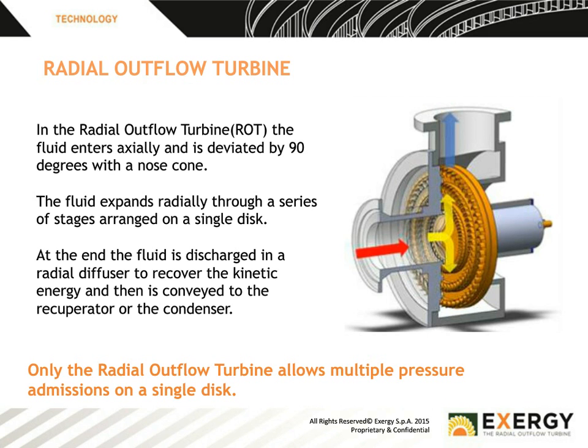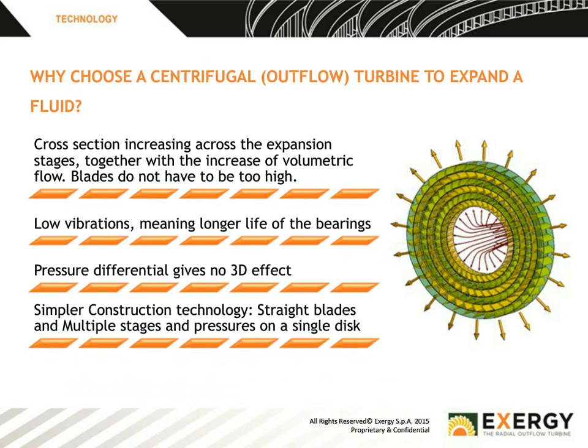So I'm going to talk a little bit about this turbine and tell you some of the key advantages. So first of all, we're going to start with a very basic advantage of the radial outflow turbine. The idea of an expansion turbine is that the fluid moves from a smaller area to a bigger area. It expands within the turbine. A very simple concept then is if that fluid moves out across a disc, it has a larger volume as it moves out across that disc all the time. So this natural expansion as it moves across the disc gives us a very, very good expansion ratio compared to an axial turbine or a radial inflow turbine, which our competitors would use.